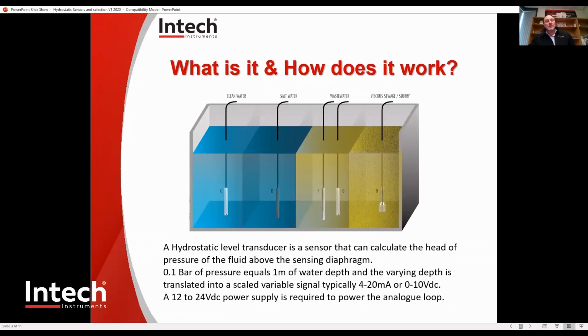As you can see in the imaging here, a hydrostatic level transducer is a sensor that can calculate the head of pressure of the fluid above the sensing diaphragm. 0.1 of a bar is approximately equal to 1 meter of water depth, and the varying depth is translated into a scaled variable signal, which is typically a 4 to 20 milliamp or 0 to 10 volt DC analog signal. A 12 to 24 volt DC power supply is usually required to power that analog loop.